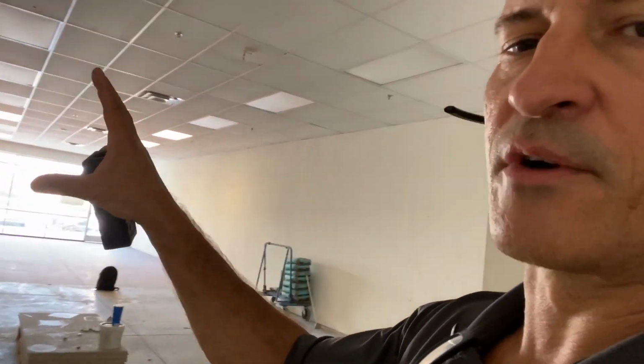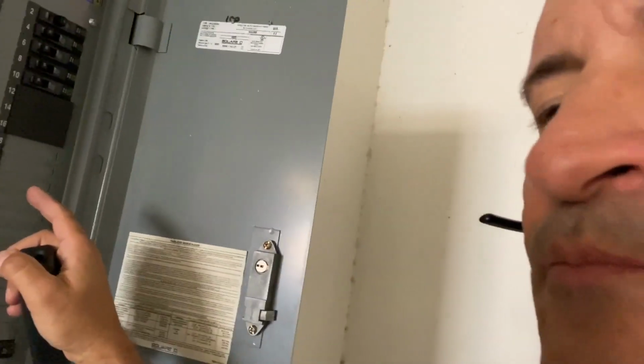You also need to control your AC from your unit. You can't have ductwork going across these demising walls. Now let's look at this here. I'm going to show you the panel. This one happens to have a schedule, and this tells me on each breaker what is in the panel. And there's some spot checking I do.